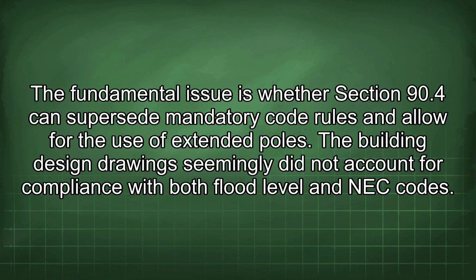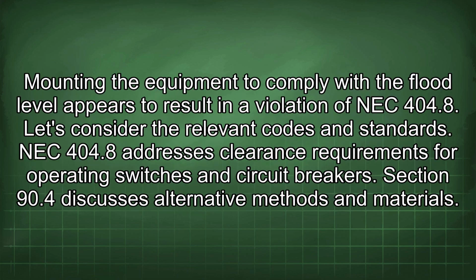The building design drawings seemingly did not account for compliance with both flood level and NEC codes. Mounting the equipment to comply with the flood level appears to result in a violation of NEC 404.8. Let's consider the relevant codes and standards. NEC 404.8 addresses clearance requirements for operating switches and circuit breakers. Section 90.4 discusses alternative methods and materials.